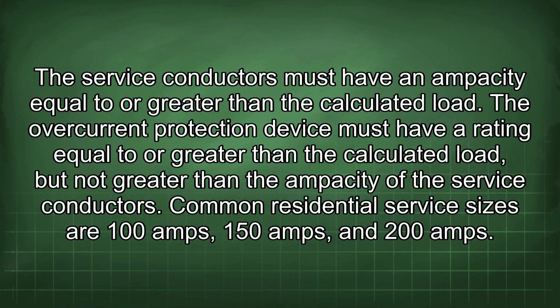The service conductors must have an ampacity equal to or greater than the calculated load. The overcurrent protection device must have a rating equal to or greater than the calculated load, but not greater than the ampacity of the service conductor. Common residential service sizes are 100 amps, 150 amps, and 200 amps.